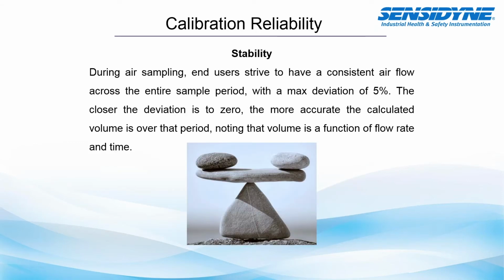Next, we're going to talk about stability. During air sampling, end users strive to have a consistent airflow across the entire sample period, with a max deviation of 5%. The closer the deviation is to 0, the more accurate the calculated volume is over that period, noting that the volume is a function of the flow rate and time.